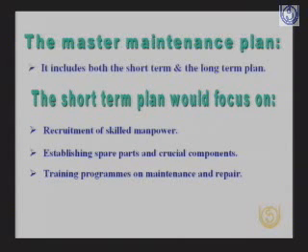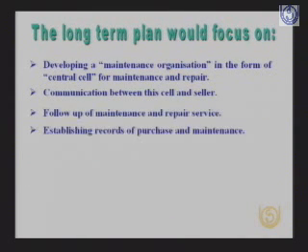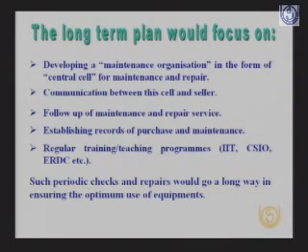The master maintenance plan, again Professor Arora mentioned about this. The master maintenance plan is something which is long-term. Master maintenance will include the short-term as well as the long-term plan. The short term would mean recruitment of skilled manpower, establishing the spare parts bank, training programs on maintenance and repair. And the long term plan would mean that any hospital of the size of a district hospital and more must have a workshop of its own.